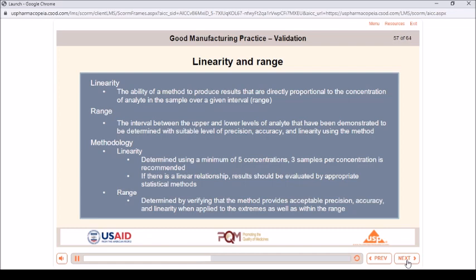Methodology. Linearity is determined using a minimum of 5 concentrations; 3 samples per concentration is recommended. If there is a linear relationship, results should be evaluated by appropriate statistical methods. Range is determined by verifying that the method provides acceptable precision, accuracy, and linearity when applied to the extremes as well as within the range.